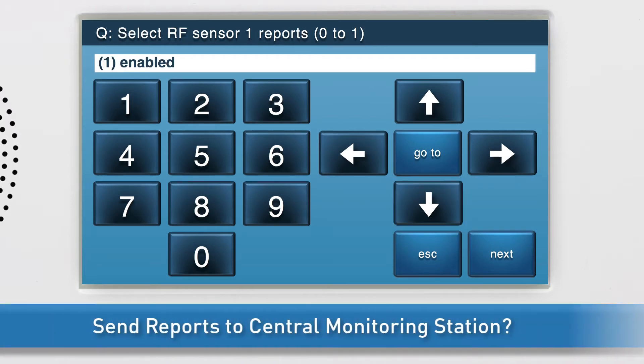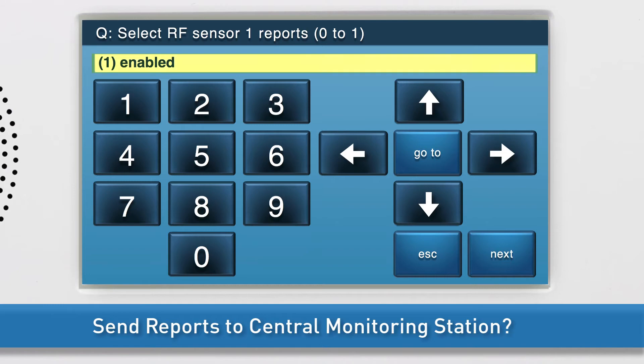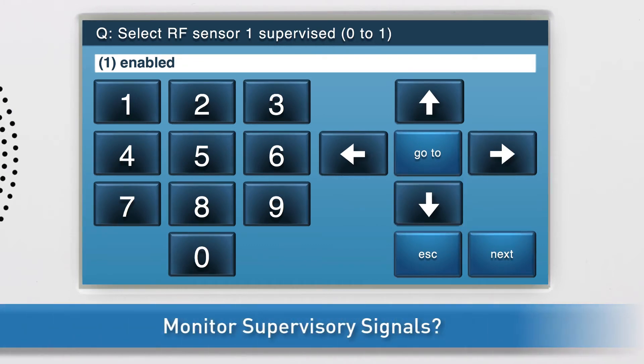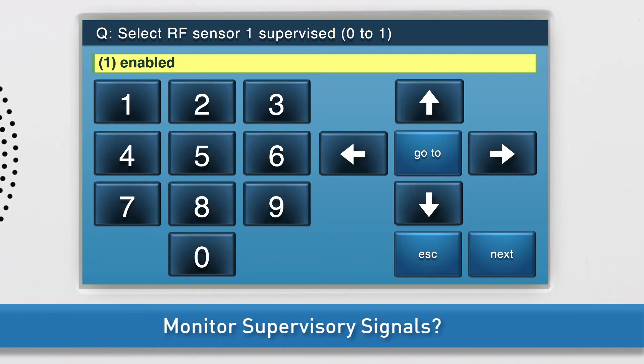Next, choose whether or not to send reports to the central monitoring station. If you would like reports related to the detector to be sent to the central station, select one enabled. Press the down arrow to go to the next sub-question. Next, decide whether or not you want the panel to monitor supervisory signals of the detector, such as low battery, tamper, and more. Select one enabled to activate this feature. Press the down arrow to go to the next sub-question.